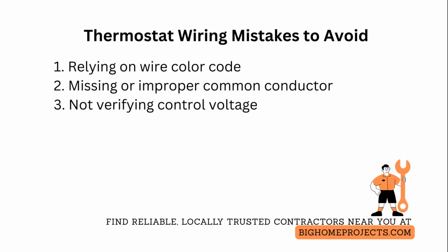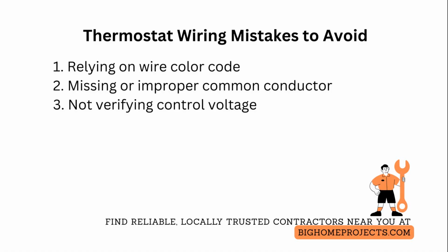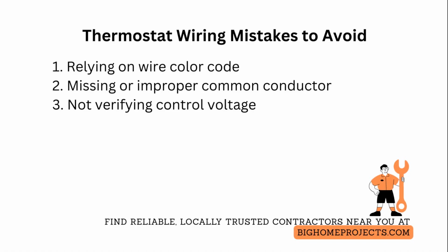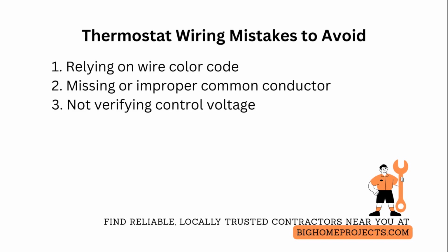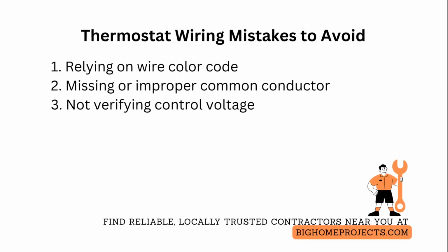One of the most common issues is a missing or improper common conductor on smart thermostat installs, which leads to battery drain or thermostat reboots. Solve it by running a dedicated common wire or using a certified power adapter or the manufacturer's supplied power extender kit, following wiring diagrams and polarity checks.